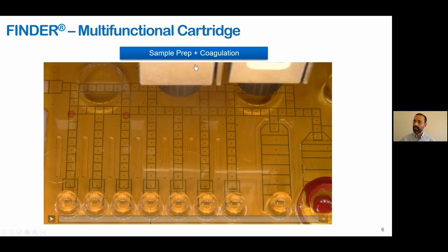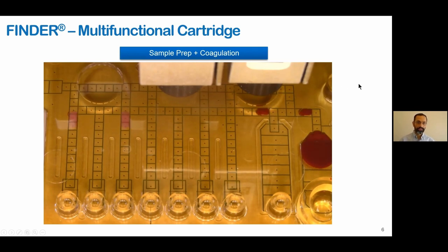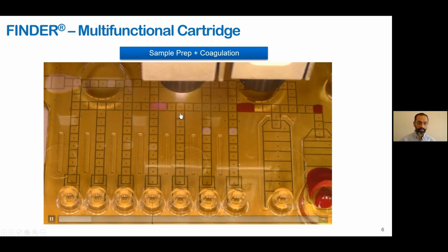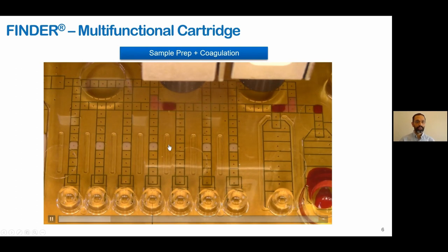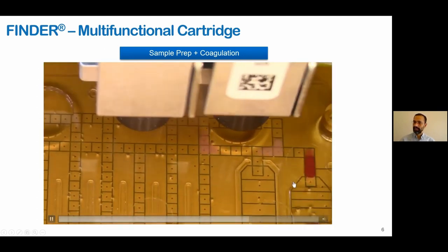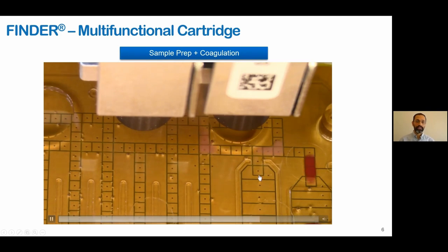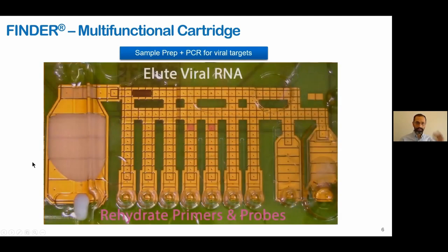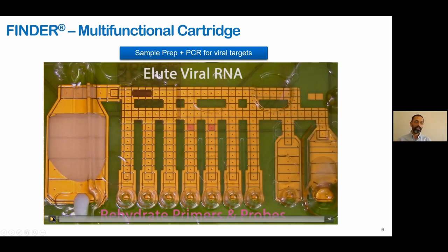Chemistry and coagulation were added on the same cartridge: plasma is prepared from whole blood, dried reagents are reconstituted on the cartridge, a rate-kinetic assay for anti-factor Xa is performed, combined with viscoelastic testing for APTT coagulation by measuring droplet viscosity as it moves back and forth. This technique can be extended to PT, fibrinogen, and other viscoelastic methods. When COVID hit, heaters and sensors were added to the cartridge to perform PCR — collecting viral nucleic acids onto magnetic beads, cleaning, and doing ultra-rapid PCR in four to seven minutes.